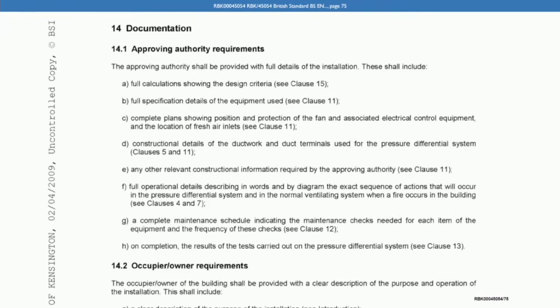Now, if we go to section 14 of this document first, on page 75, this section provides guidance on how to document the commissioning process, and what the approving authority, that would be building control, should be provided with. Were you familiar with these requirements? Yes, I've read them several times. And we can see from the list: full calculations showing the design criteria; full specification details of the equipment used, that's in B; G is a complete maintenance schedule indicating the maintenance checks needed for each item of the equipment and frequency of the checks; and then H, on completion, the results of the tests carried out on the pressure differential system. Do you see that? Yeah. And then if we can go to another British Standard, that's BS 7346 Part 8. This is at LAK 50242.